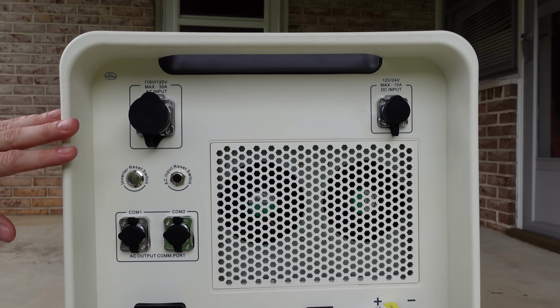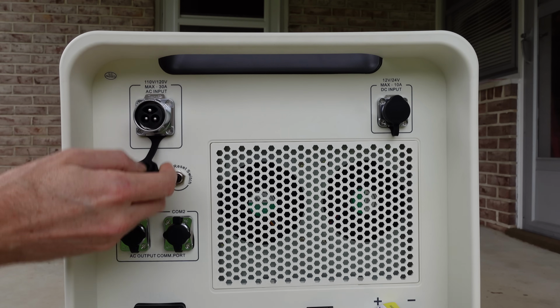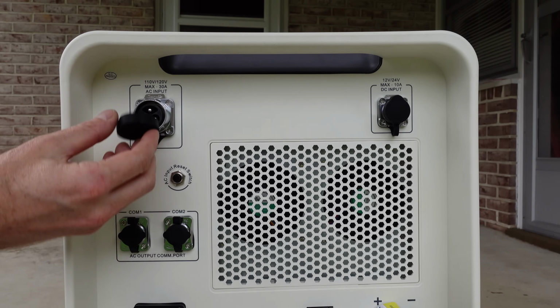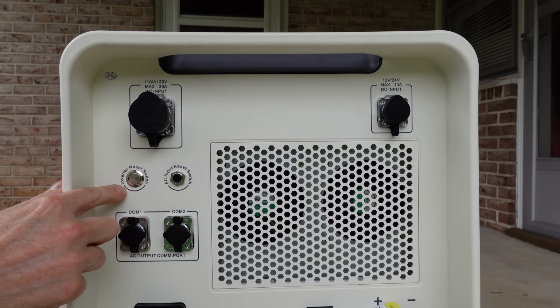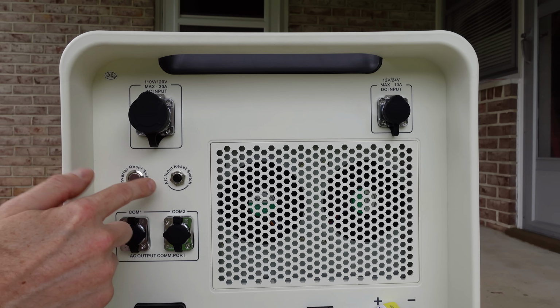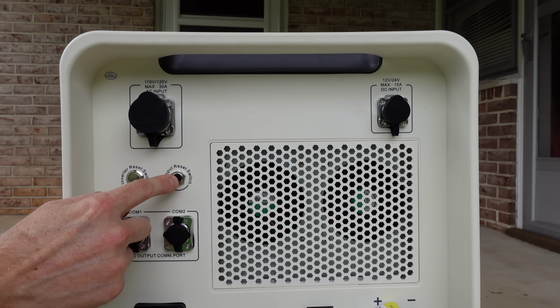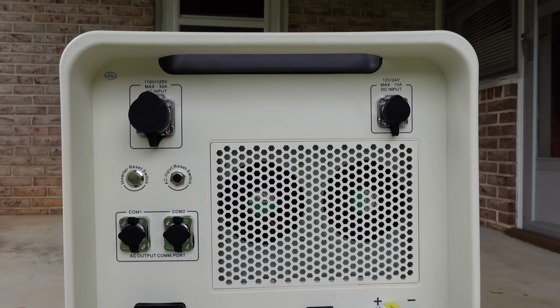On the rear of the device, starting with the top, we have our AC input. This is 120 volts at 30 amps. We have a reset push switch for the inverter, and an AC input reset switch. This looks like it might be actually a circuit breaker. We have 2 communications ports if you're going to connect multiple of these together, or additional batteries.